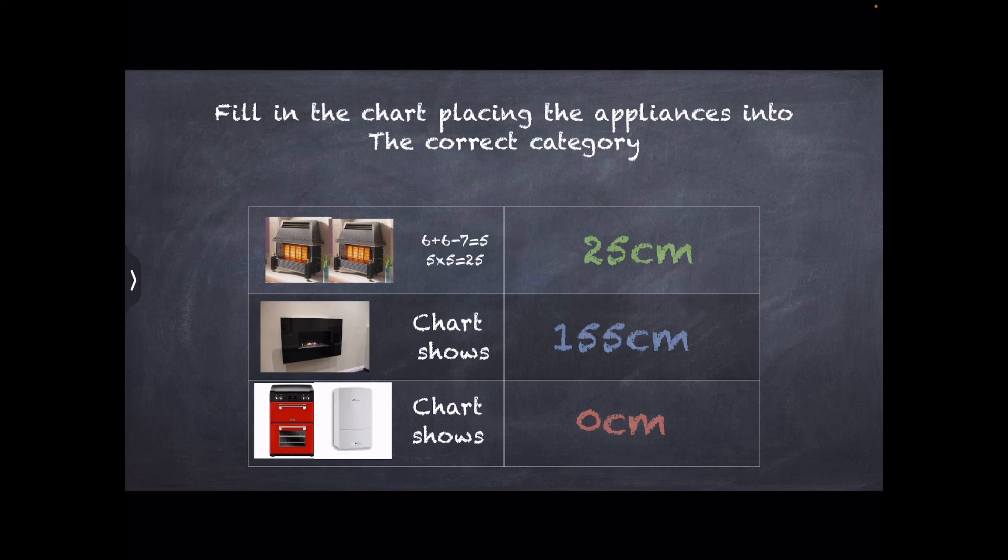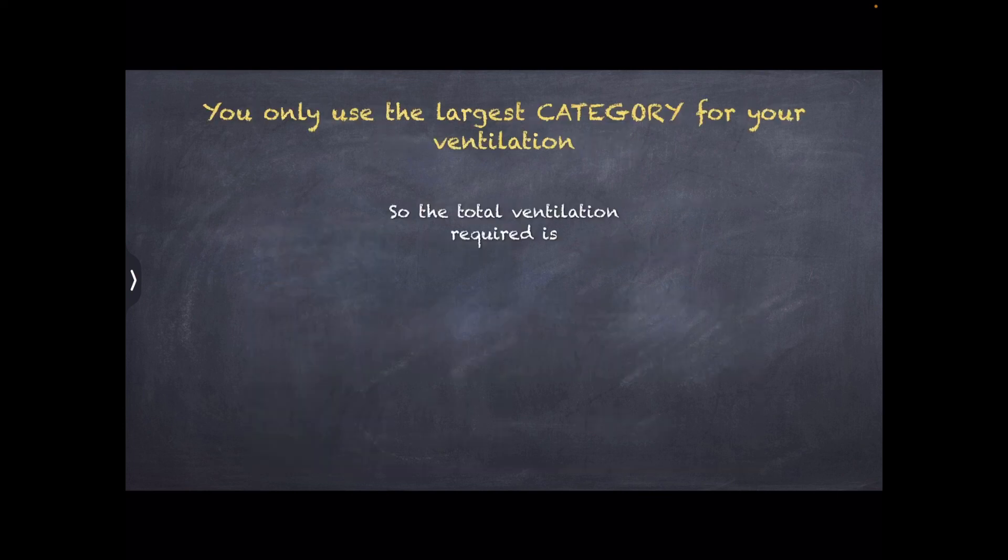That's your basic chart showing you how much ventilation is required for each category. Not for each appliance, for each category. The largest one of these is the flueless space heater category. So, and here's the bit that confuses everybody: you only use the largest category for your ventilation.